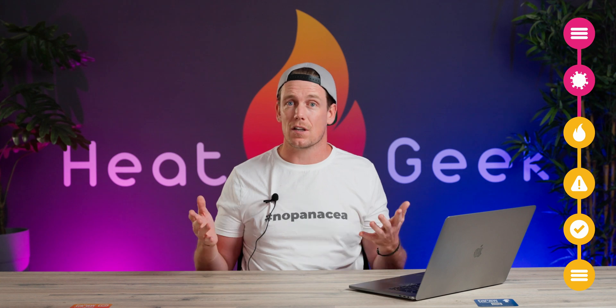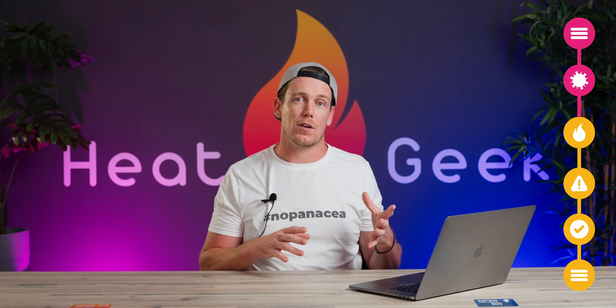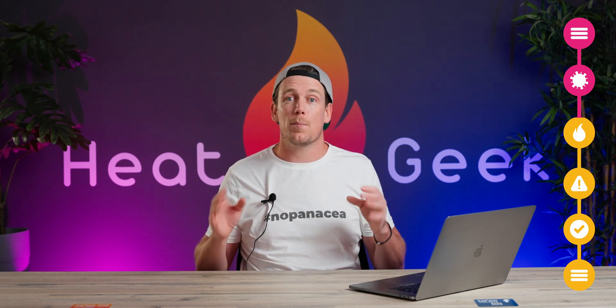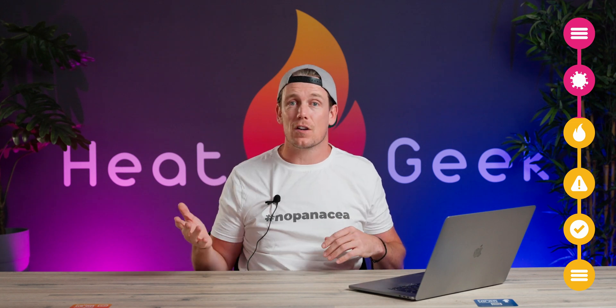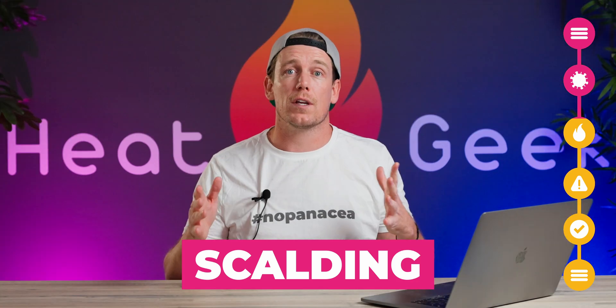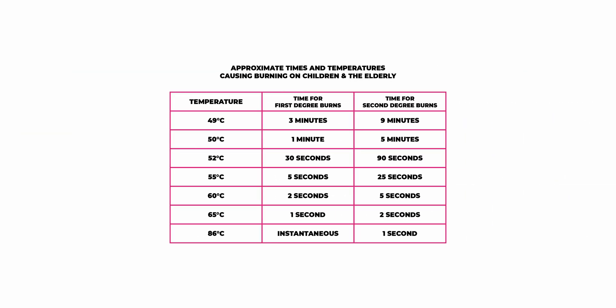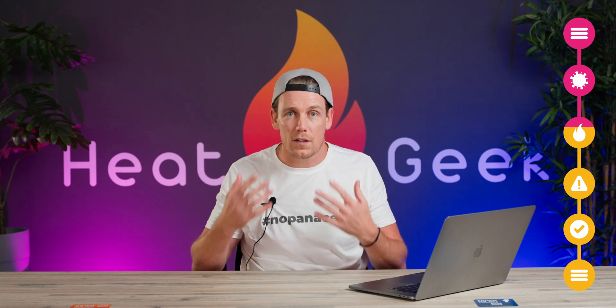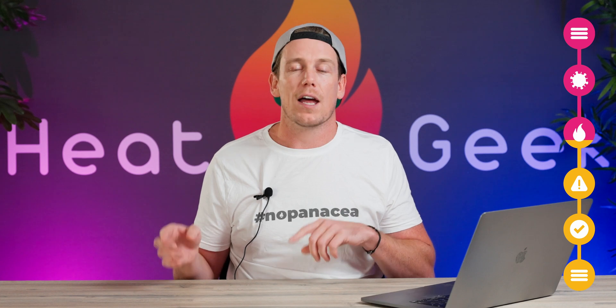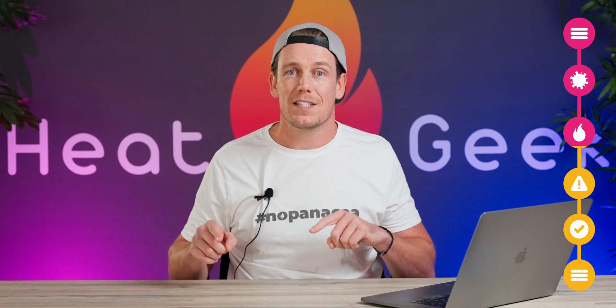Now you could keep the hot water at 70 degrees and be incredibly safe from Legionella growth, but as the most common place for Legionella bacteria to survive in domestic properties seems to be shower heads, this won't help — shower water is typically blended down to 37 degrees, which happens to be the perfect temperature for Legionella growth. In fact, anything over 50 degrees can cause scalding and water at 60 degrees can only take one second to cause serious burns. Setting hot water to 60 degrees for a vulnerable person can be very dangerous. Take a look at this table — first degree burns happen in just two seconds for the elderly and the young at 60 degrees. This is exacerbated by the time it takes for the brain to register the temperature, which increases as you get older. For this, we suggest following the Part G regulations and not storing at 60 degrees Celsius or above unless you have scalding protection fitted at the outlets.